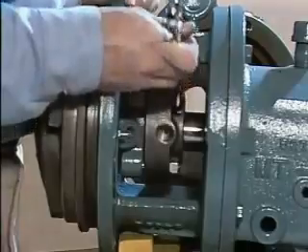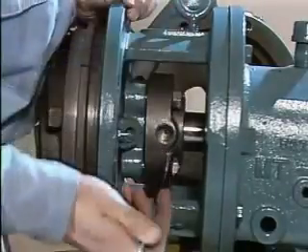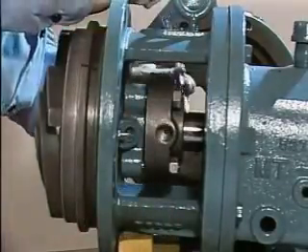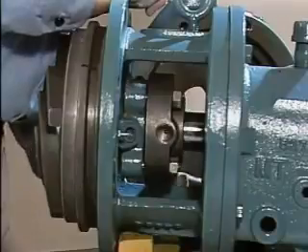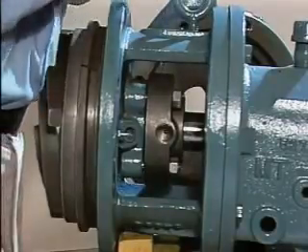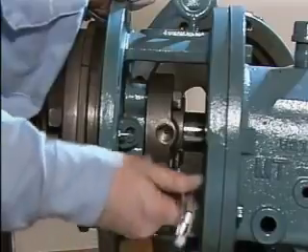Another way that the seal face gap can widen is if either seal face becomes distorted or warped. One cause of seal face distortion is over-tightening the gland bolts during installation. Another cause of seal failures is overheating. Heat is often a part of a machine's operation, and mechanical seals are designed to function under those conditions. But sometimes the heat becomes so severe that the seal parts begin to break down.